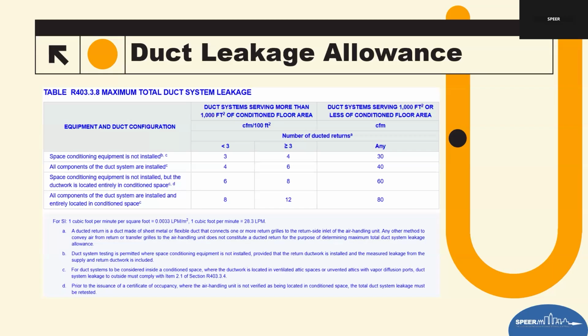So there are some footnotes to call out here. Footnote B: you can test without the air handler, but you must test again before occupancy if treating the ducts as inside conditioned space. Footnote C basically says ducts in the attics with vapor diffusion ports, again, I'm not sure we'll see that in Texas, do not automatically count as inside conditioned space. It must meet the requirement of R403.3.4. And then footnote D defines how ducts entirely in conditioned space is determined.